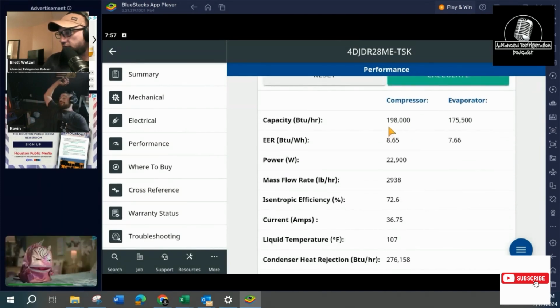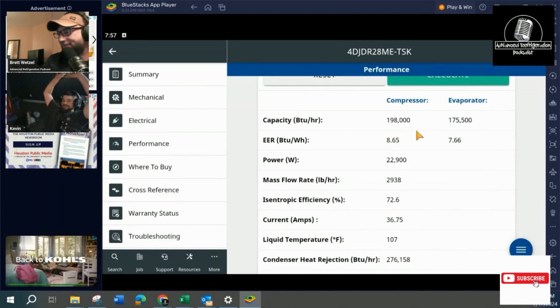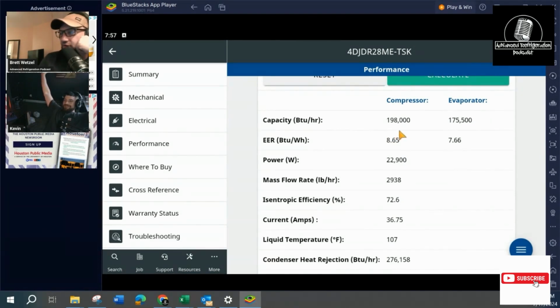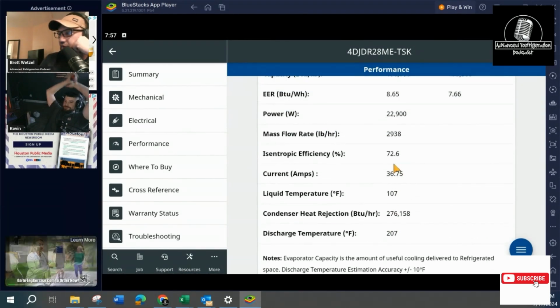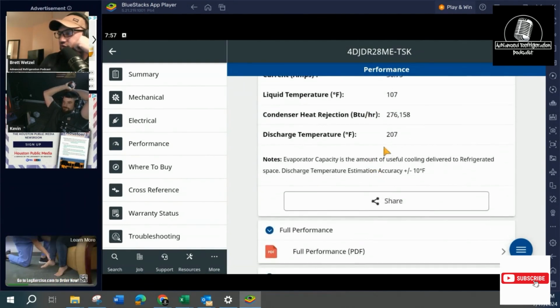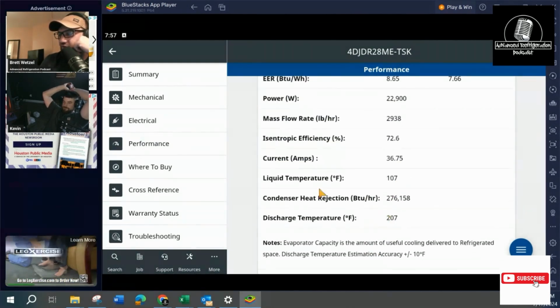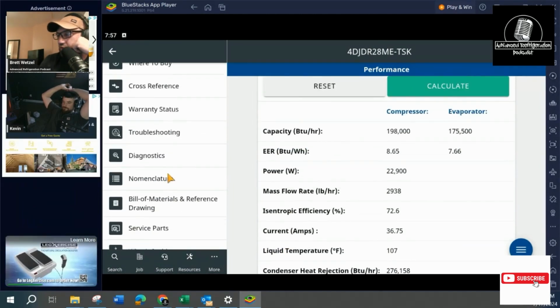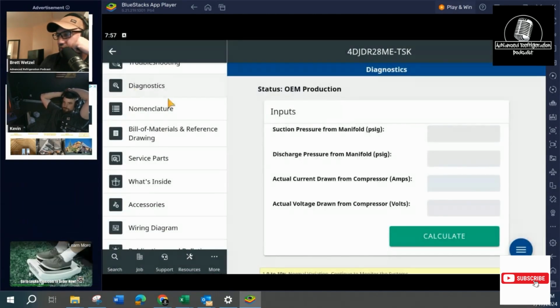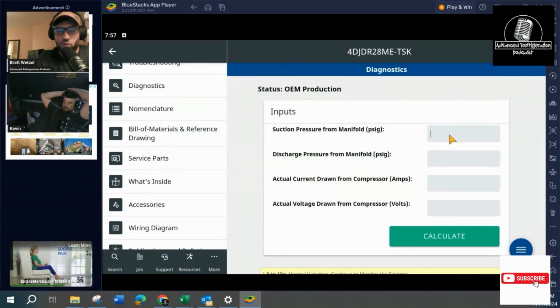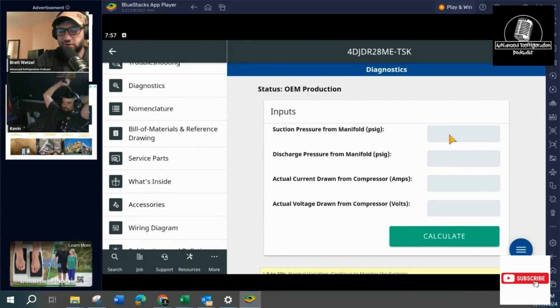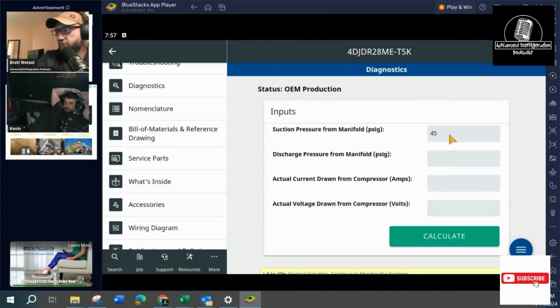Oh, right. Sometimes you'll have those on those big jobs. Yeah, 198, so 198,000 BTUs. Okay, so we have 36.75 amps. Great. Discharge temperature of that compressor 207. Great. But then watch when we go over to diagnostics. Right now, we plug in what we should have had. Oh, now this is going to make me think. 20 degrees saturated on 449. It's basically what, 45 pounds or something like that?